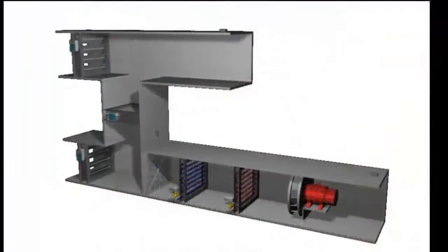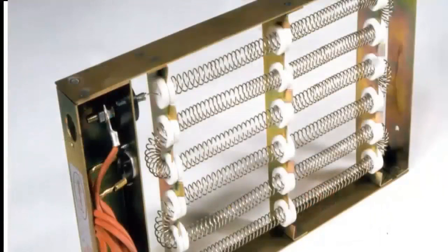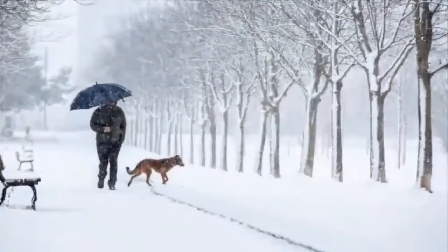Twenty-third, if you are in a cold part of the world where the air temperature reaches or is close to freezing, you have a pre-heater on the fresh air intake — it is usually an electric heater. When the outside air is around 5 degrees Celsius, the heater will turn on and heat the air to protect the components inside from frost. Otherwise, this could freeze the heating and cooling exchangers inside.